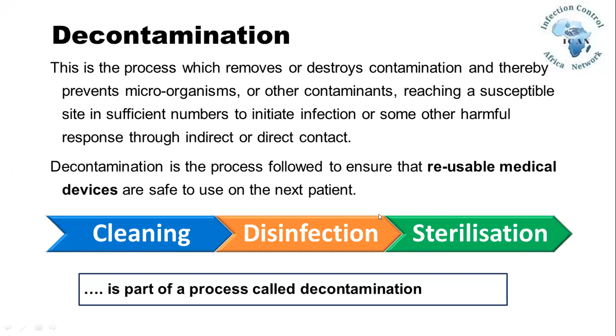Looking at decontamination, we know it's a process which removes and destroys contamination and thereby prevents microorganisms and other contaminants from reaching a susceptible site in sufficient numbers to initiate infection or some other harmful response through direct or indirect contact. Decontamination is a process followed to ensure that reusable medical devices are safe to use on the next patient. And please believe me, you might be that next patient. It includes cleaning, disinfection, and sterilization. Cleaning is the physical removal, using a detergent and water, of soil or contamination, such as organic material, from surfaces or objects, making them safe to use or touch. 80 to 90% of microbes are then removed.